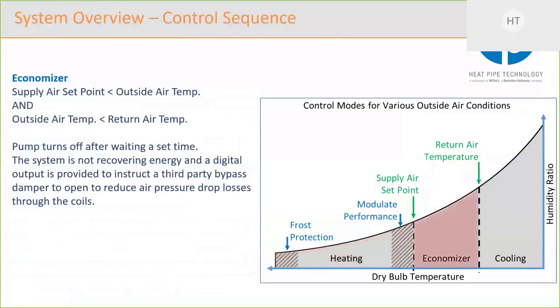So the middle regime is economizer. This is officially still heating mode, but the problem is we're already above the set point. The outside air is already above the set point. So what happens there is your pump is already running at minimum speed, you're bypassing all your water, and the system realizes this and turns the pump off. It essentially goes to sleep, and it will monitor the conditions around it and wake up when it needs to leave economizer mode.